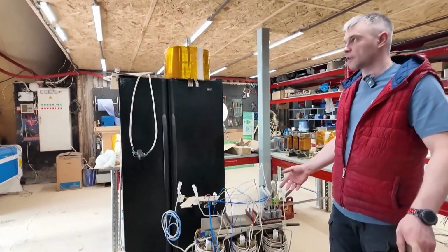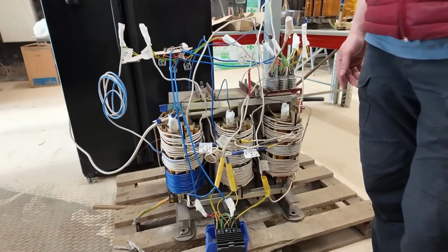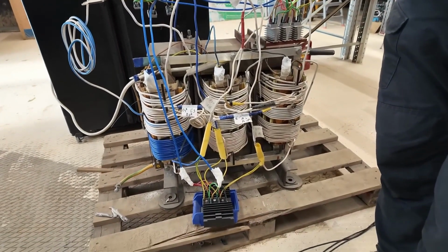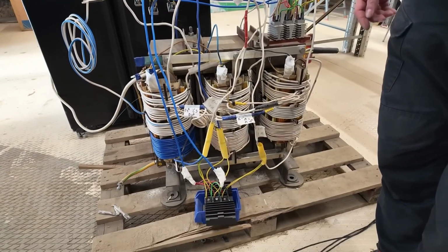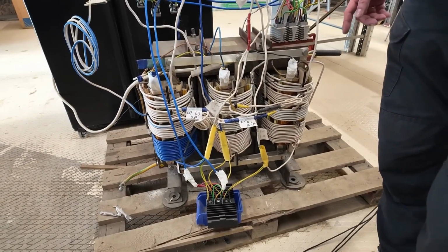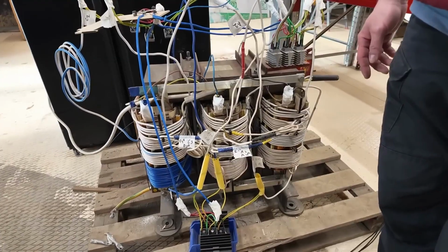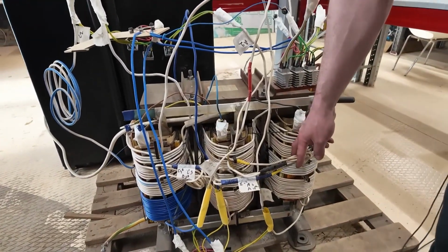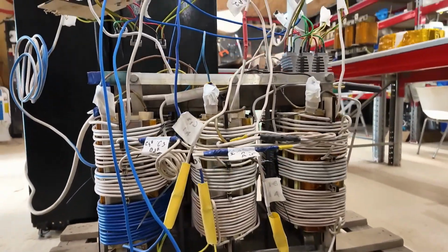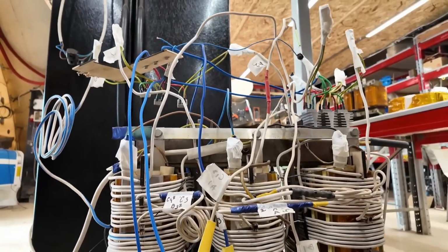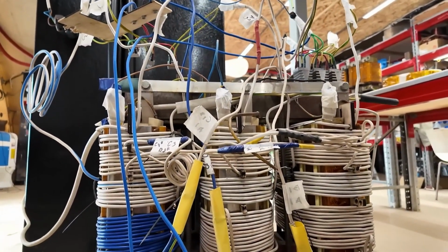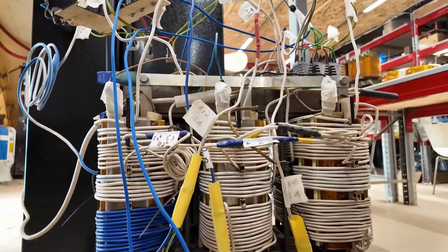So, Mikhail, what do we have here? This is the main primary power transformer for our test stand. We had a 160 kilowatt uninterruptible power supply, or UPS, that unfortunately burned out. After that, we took the transformer from this unit and carefully wound our own custom winding on it, so as to get what is known as an 18-pulse rectifier, which is quite significant in this context.